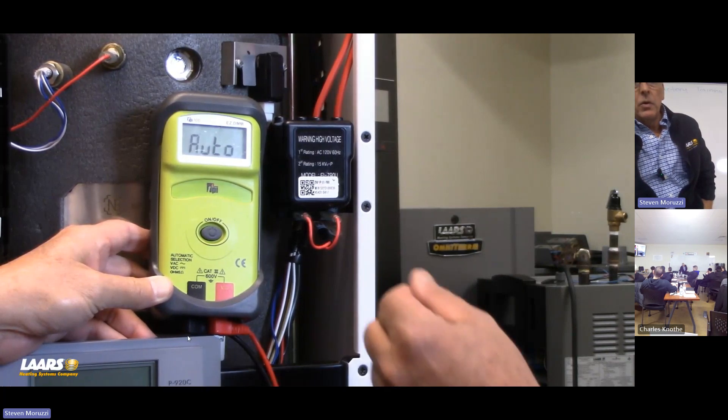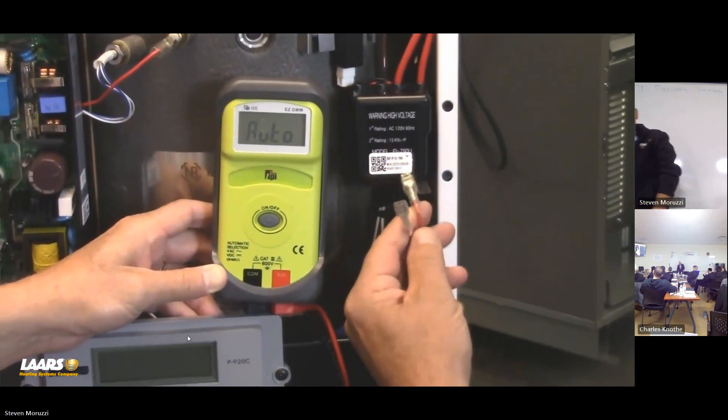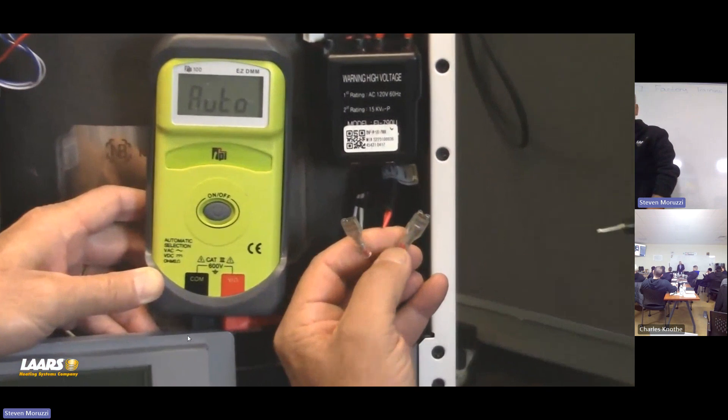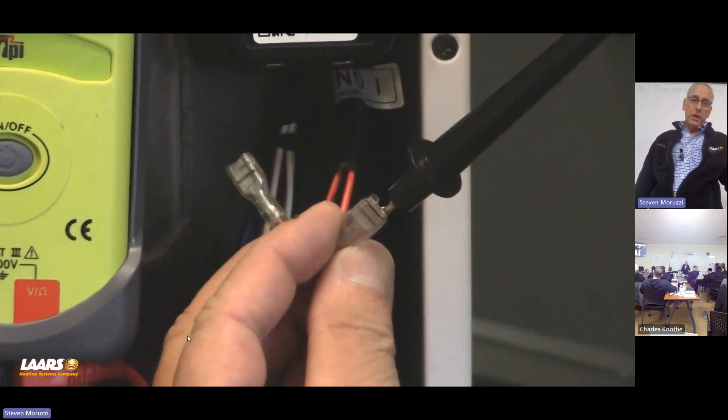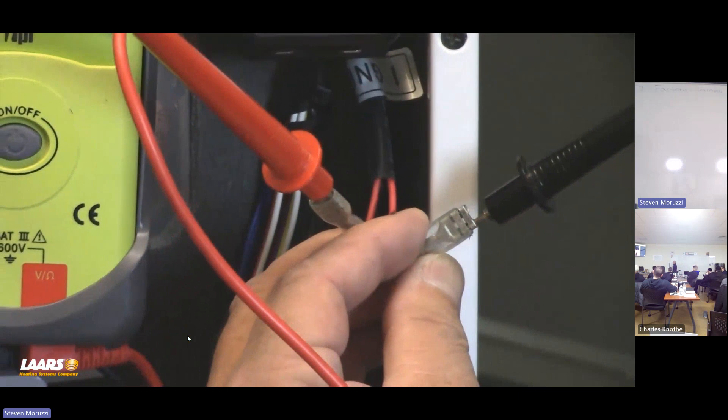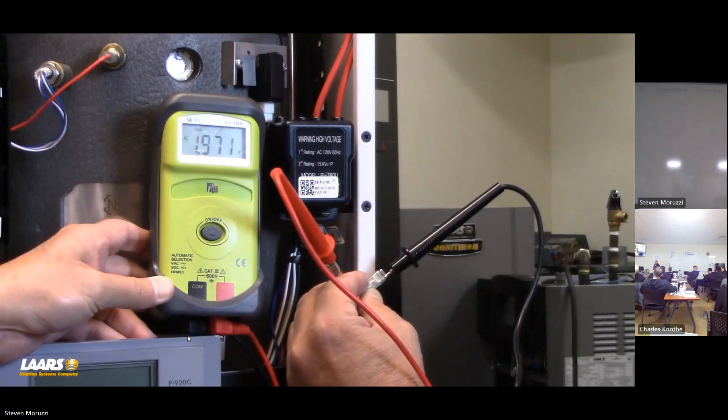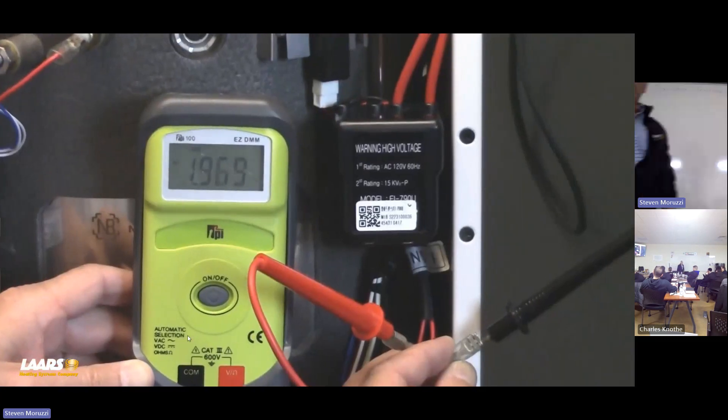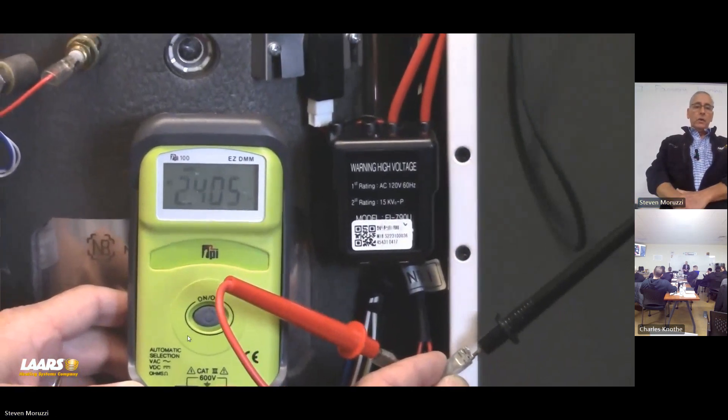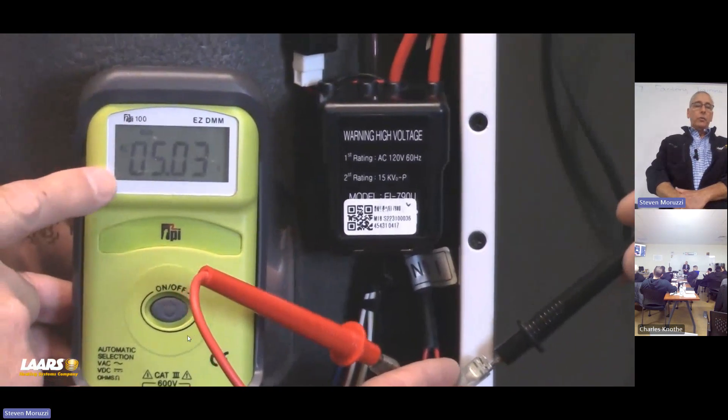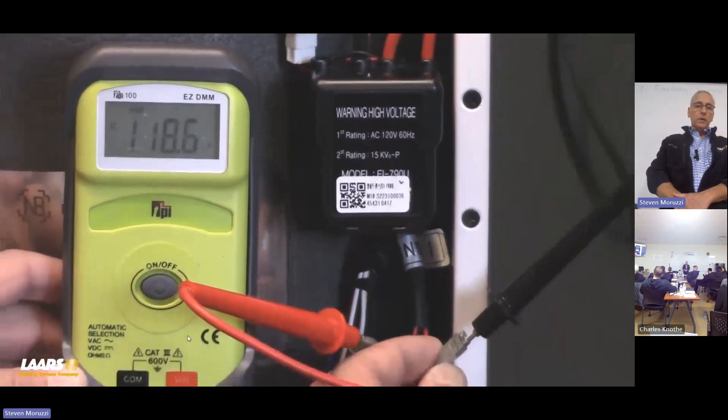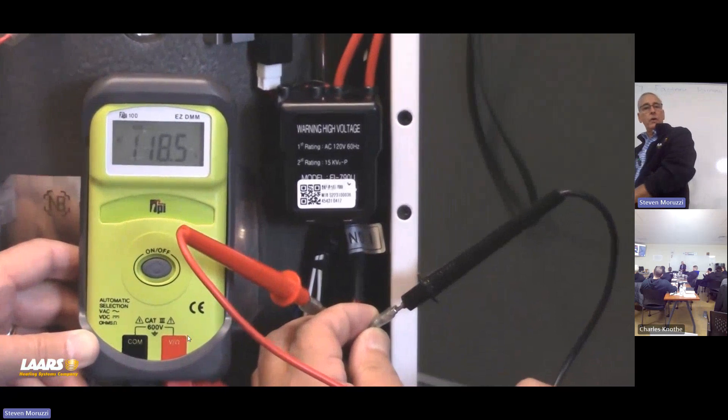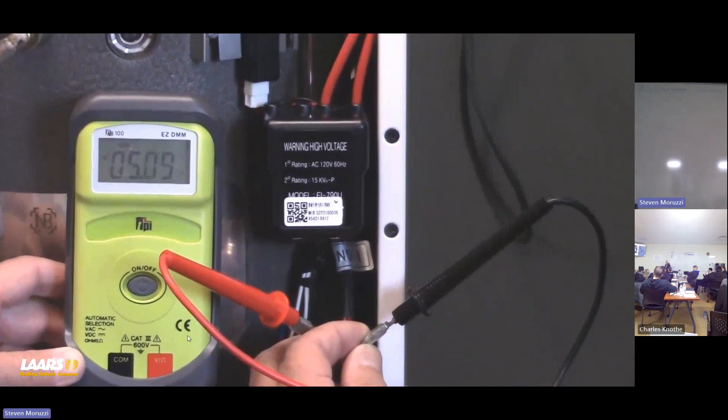Here we're going to show checking your spark transformer. We're going to put a volt meter here. First of all, we recommend power off the boiler, put your meter leads in, power the boiler back up. Should I be reading 120 volts here right now? No, because I haven't gone into ignition yet. If you look at that volt meter right now, I'm only reading 1.9 volts. It's going to have a pre-purge, go through its sequence, and then we're going to energize that spark igniter. Right there, now I've got 118 volts for about four seconds or three seconds. That's my trial for ignition.